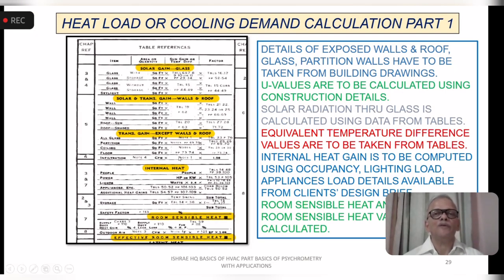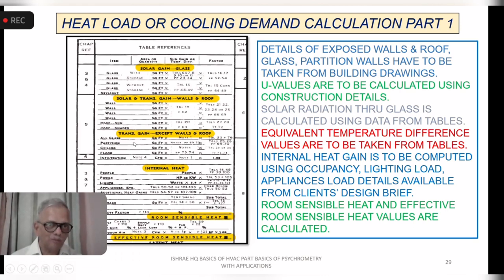So this is part one of the calculation sheet. This takes you to the room sensible heat and the effective room sensible heat. The details of exposed walls, glass, partition walls have to be taken from the building drawings. U values are to be calculated. That's a part of the heat load calculation. Solar radiation through glass is calculated. Equivalent temperature differences for the walls have to be taken from various tables. Internal heat gains are to be computed. So after doing all this exercise, you get this solar gain, solar plus transmission, internal; all this is the room sensible heat and the effective room sensible heat with the bypass factor. And that's the difference with the ASHRAE method.